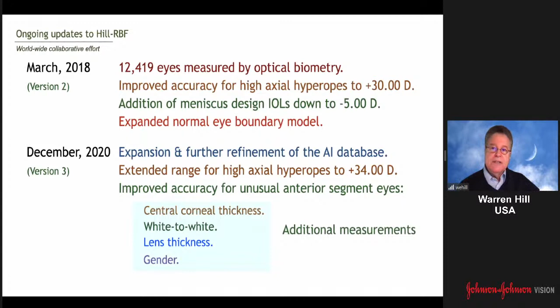Now to show how much of an improvement this is, we're going to look at a high axial hyperope, and you can see with version 2, every one of the calculations is red, which means it's out of bounds on this Excel spreadsheet. For version 3, every one is inbounds now. We look at a high axial myope, in this case an extreme axial myope. In version 2, we have limited options for the refractive target. For version 3, all options are inbounds calculation.